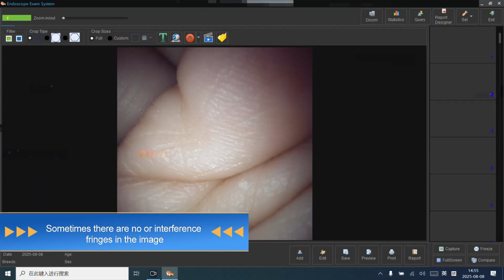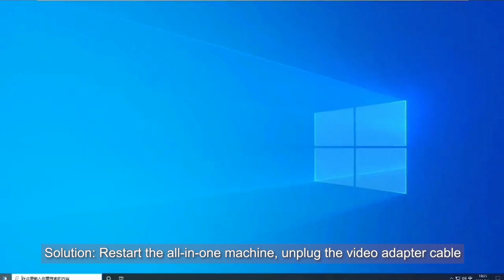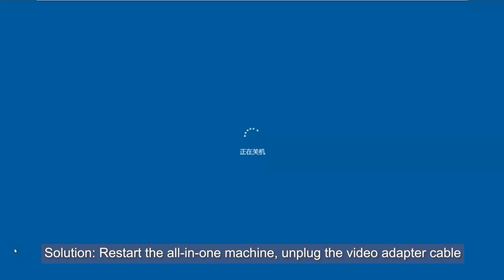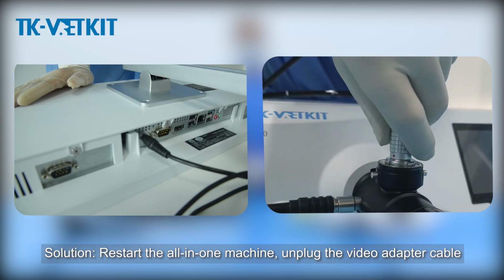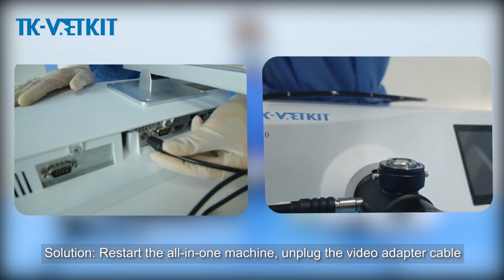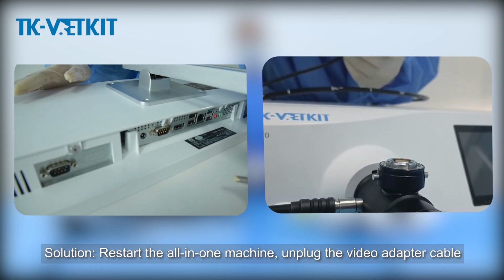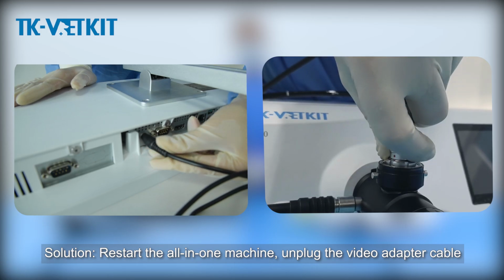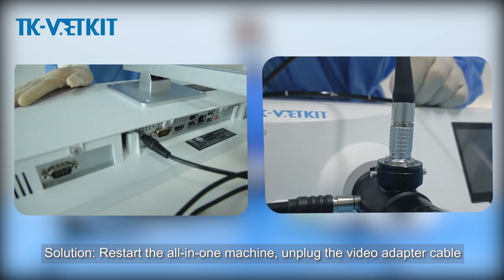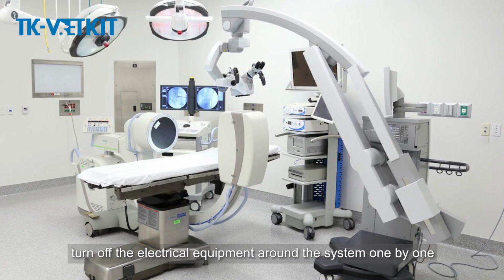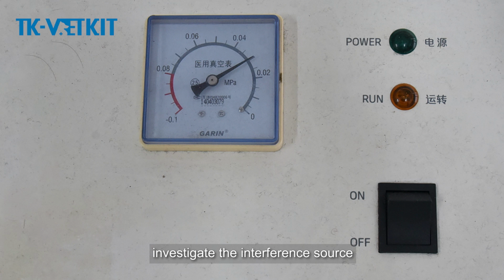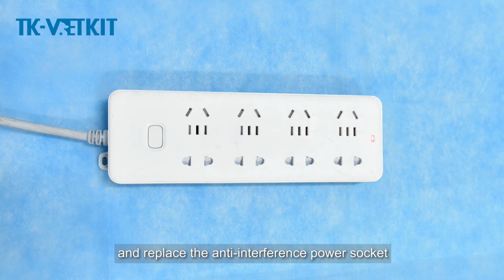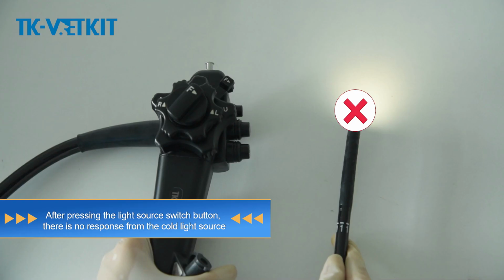Sometimes there are no images, or there are interference fringes in the image. Solution: restart the all-in-one machine, unplug the video adapter cable. Turn off the electrical equipment around the system one by one, investigate the interference source, and replace the anti-interference power socket. After pressing the light source switch button, there is no response from the cold light source.